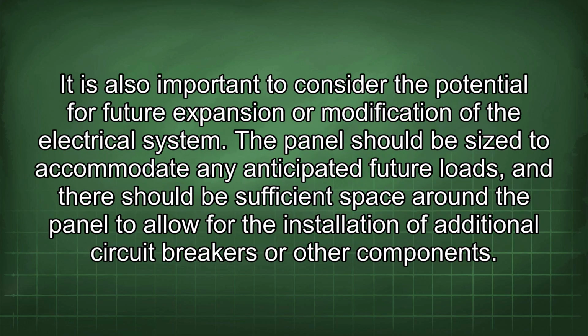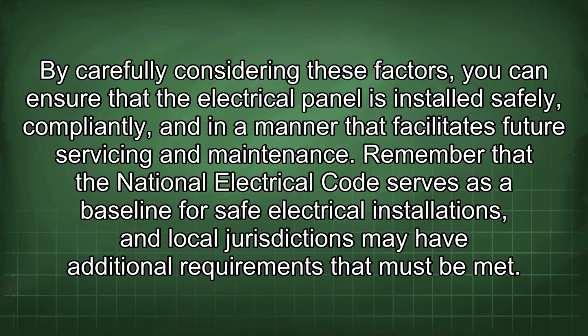It is also important to consider the potential for future expansion or modification of the electrical system. The panel should be sized to accommodate any anticipated future loads, and there should be sufficient space around the panel to allow for the installation of additional circuit breakers or other components. By carefully considering these factors, you can ensure that the electrical panel is installed safely, compliantly, and in a manner that facilitates future servicing and maintenance.